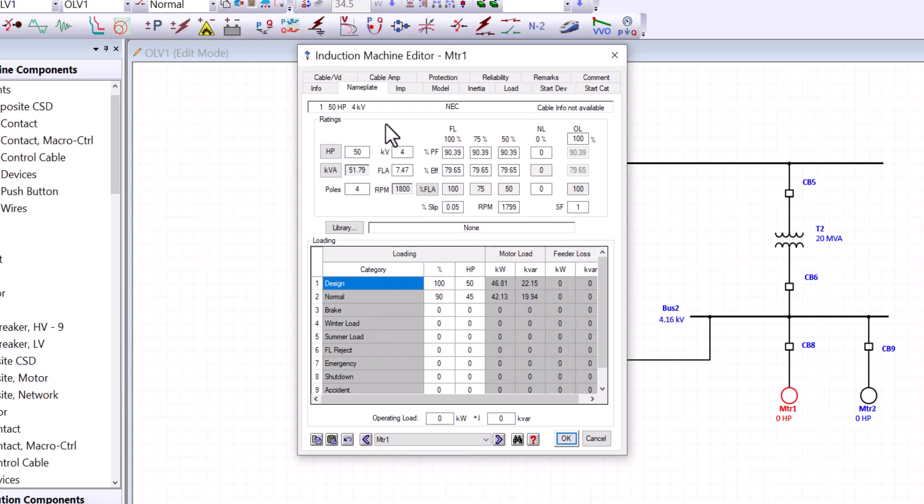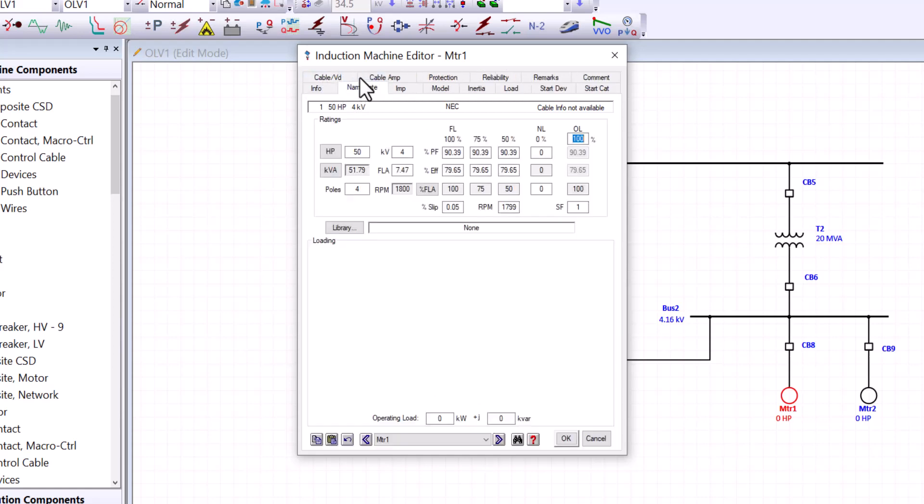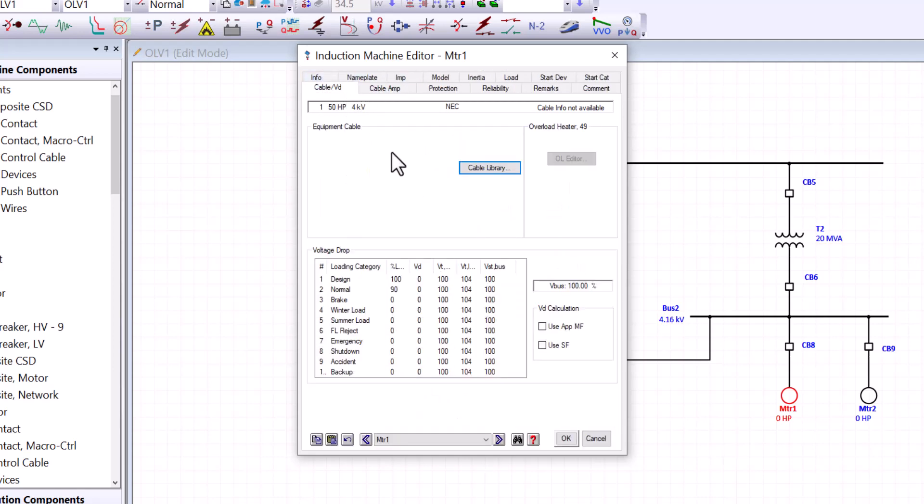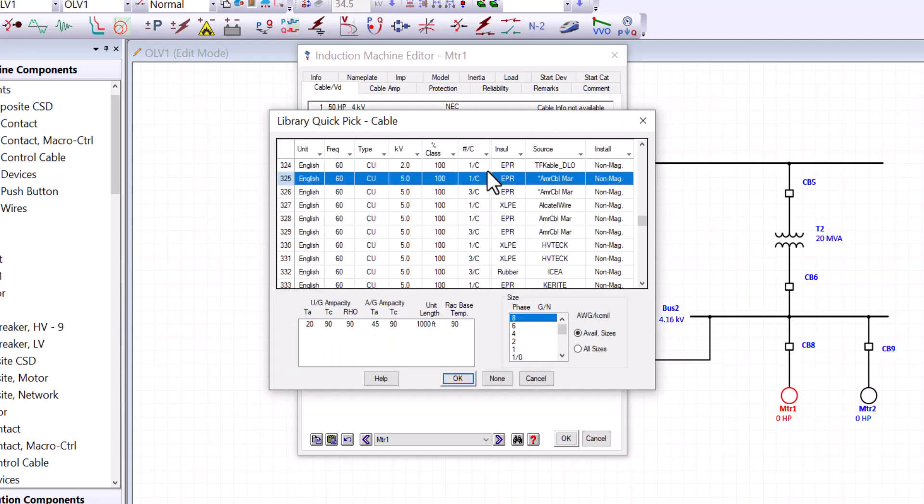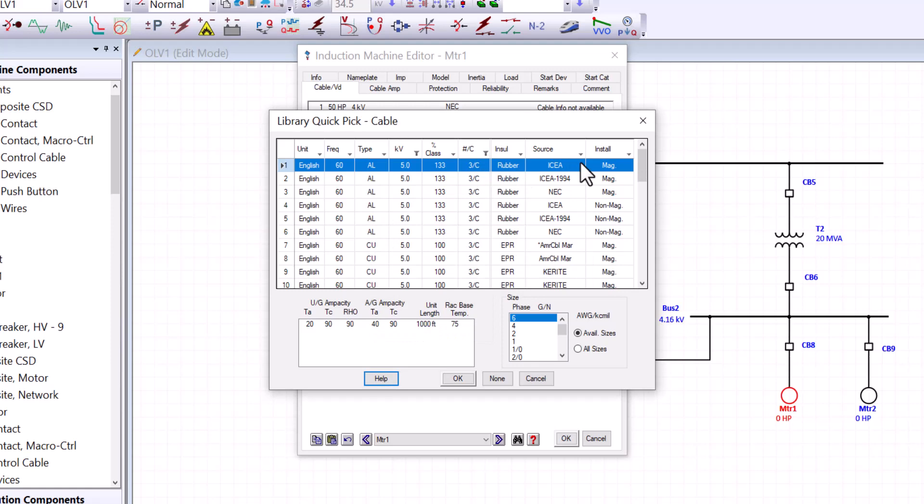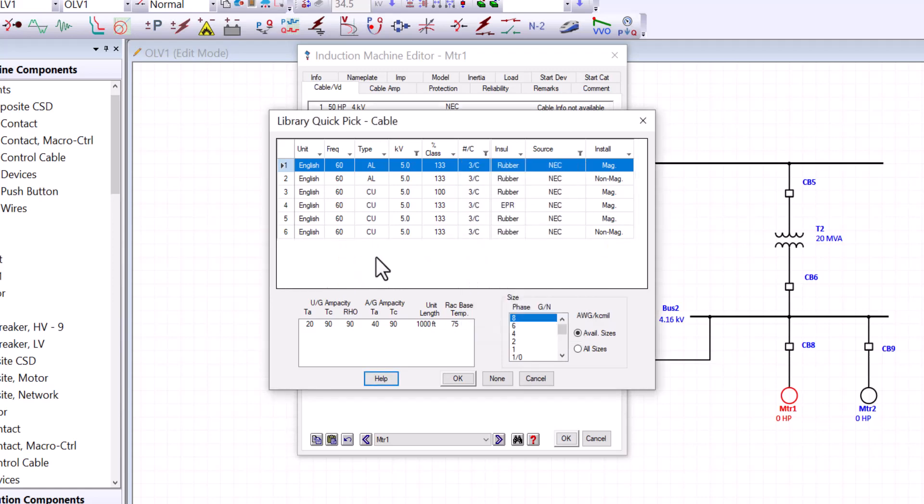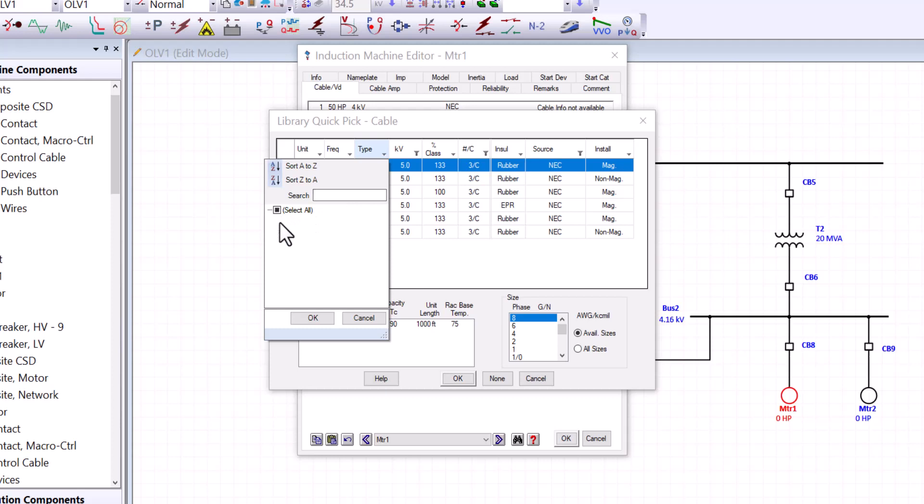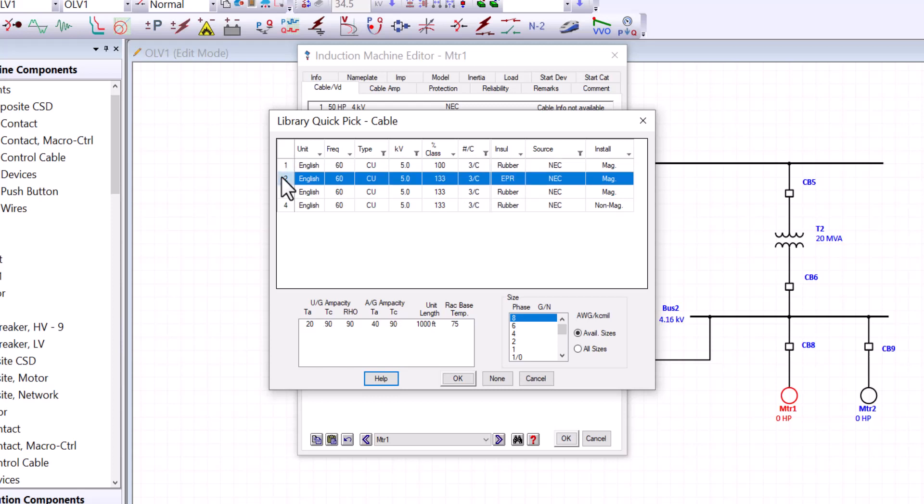There is another piece that needs to be discussed beside the nameplate. And that is the cable data. And for the example we are using here, we are using a cable from the library. So let's go here. And we are going to use a cable that is suitable for 5kV system. And we can filter that. A three conductor cable. And then the source of my data would be the National Electrical Code. And we are not using aluminum. So we can take that away. And from here, you choose the EPR. Just double click on that line.